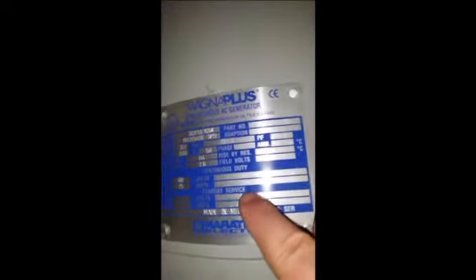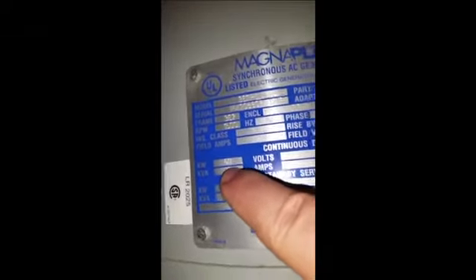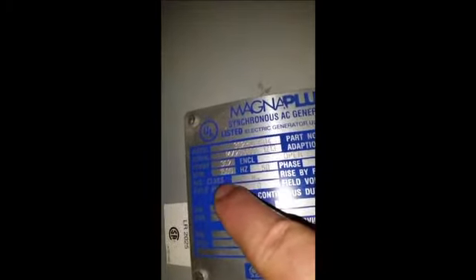The gearbox and speed control motors are controlled by a 60 kilowatt Marathon synchronous AC generator. This is a 60 Hz at 1,800 RPM or 50 Hz at 1,500 RPM, 3-phase, and the voltage can be set from 380 to 600 volts with a power factor of 80%. All AC generators are rated at an 80% power factor. We take the power and feed it into the power queue that will increase the power factor to 97 to 98%.